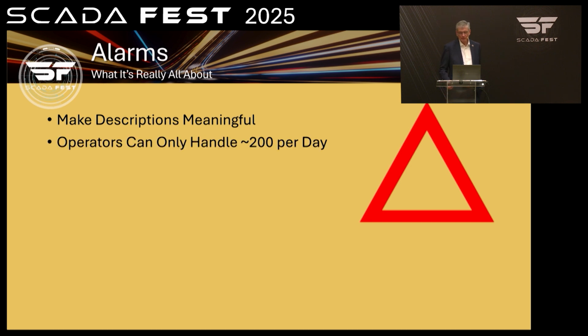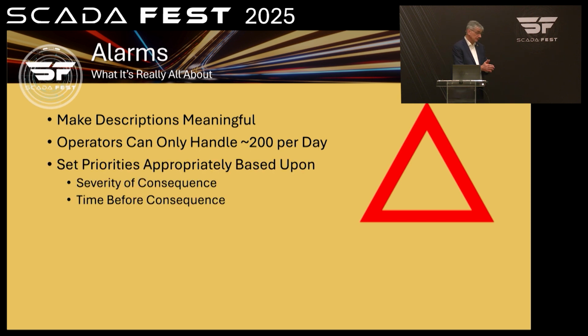And another thing, operators get fatigued with alarms. If they start to see more than about 200 a day, they just zone out. They can't deal with it. It's too much happening. I go to the bathroom and suddenly, oh, another 10 alarms to acknowledge. You need to get the alarms down to meaningful things, so it needs to get down to less than 200 a day. That means nuisance things need to be made an event, or something that's not really critical to draw someone's attention to. Or you have to split your system into different zones, so that this zone is handled by one person and that zone is handled by another person, so that they are not overloaded.